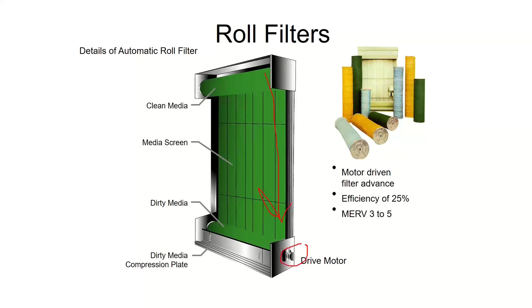So those are the simple panel filters. You can also have panel link filters, but those aren't very common anymore. You can have roll filters too, but you're never going to see these. I've only seen it once ever. The idea was that it was self-cleaning, with a little motor that would pull a new section of filter across whenever the pressure drop got high. It's a nice idea, but the motors would die out over time and people would forget about them. It's just a reason to neglect your system. Nobody uses that anymore.